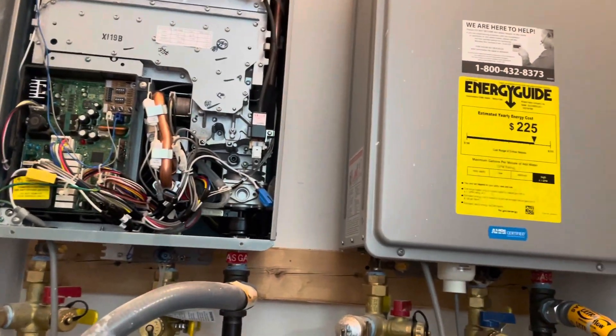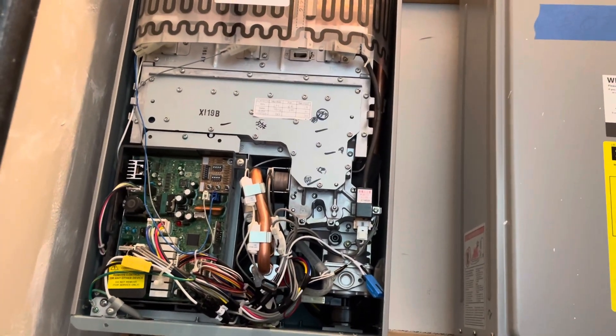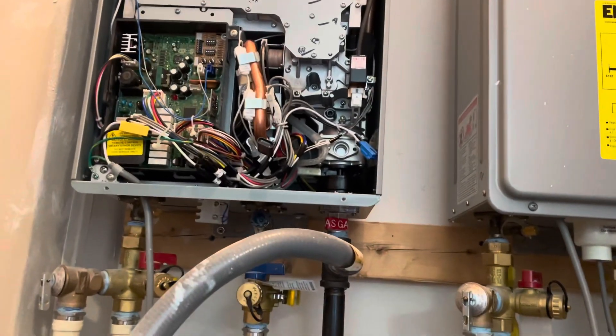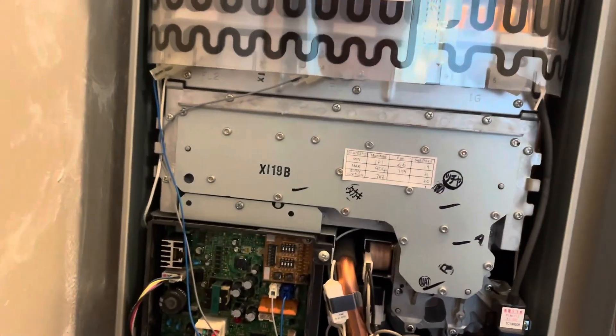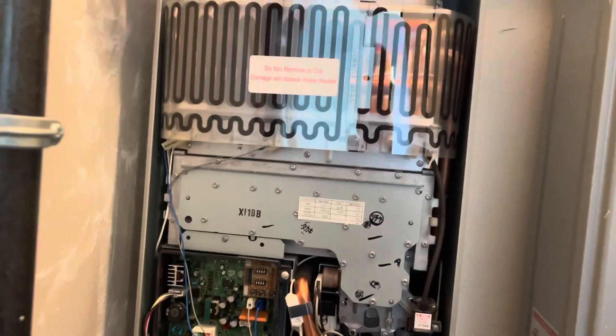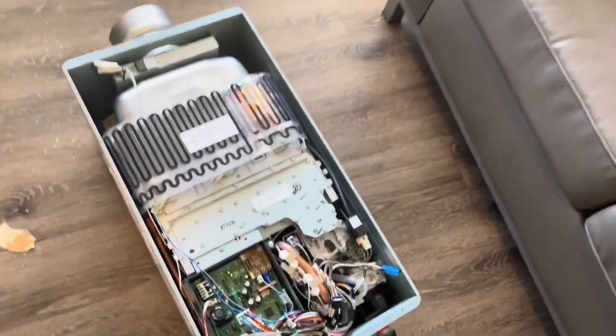We have a Rheem tankless water heater here throwing a code that indicates the burner needs to be cleaned. One of our plumbers originally looked at it and came to the conclusion that the burner needs cleaning. We're going to do that today. We have to pull it off the wall because a connection was disconnected and we can't get it back without pulling it off. Once it's out of the closet, we're going to pull the burner apart using the disassembly instructions.